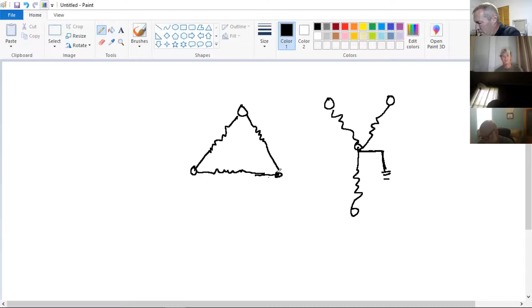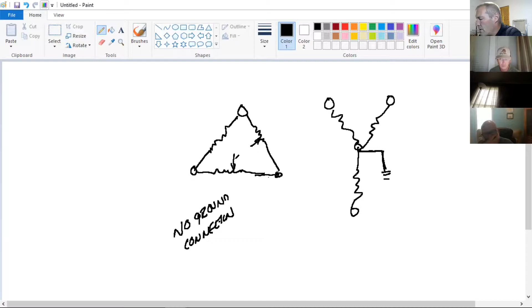One of the things about how delta works is that it operates on the difference of potential between each phase. So when this phase in my generation is at full 7,200 volts, is this other phase also at full 7,200? No - remember in generation I'm doing this, then that, then this. Nothing's ever the same as far as my wave.